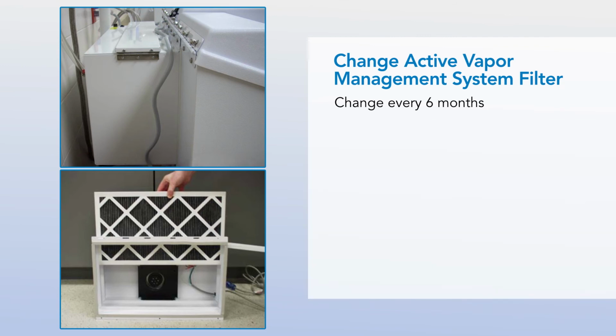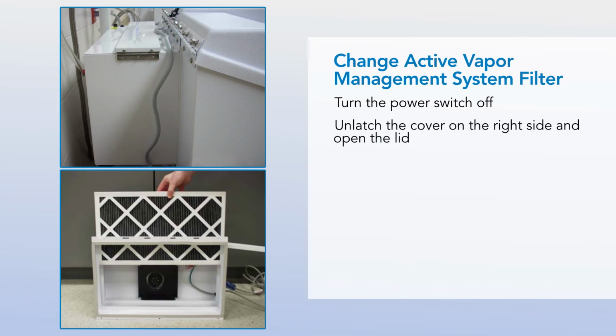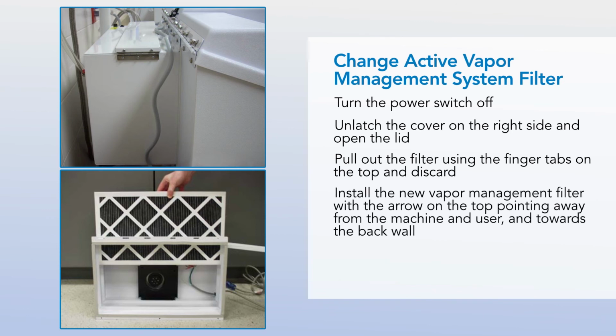To change the vapor management filter, turn the power switch off. Unlatch the cover on the right side and open the lid. Pull out the filter using the finger tabs on the top and discard. Install the new vapor management filter with the arrow on the top pointing away from the machine and user and towards the back wall. Close and relatch the lid. Turn the power back on. Document the filter change in the filter change log.